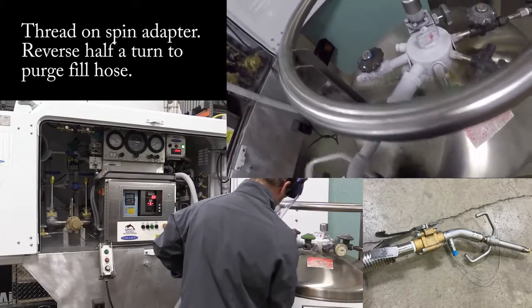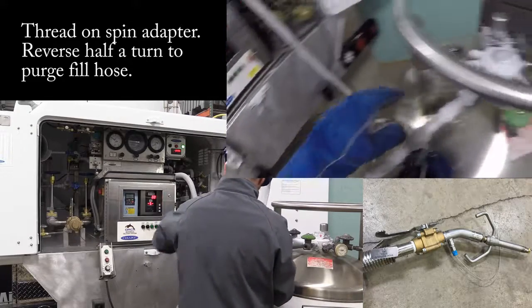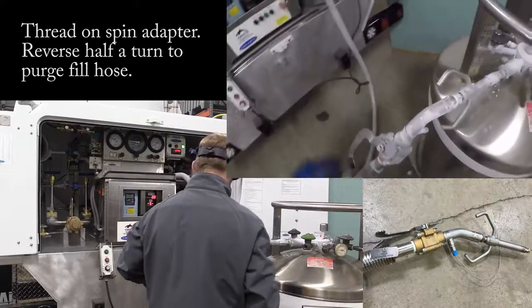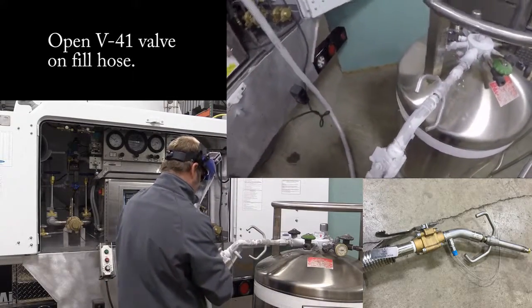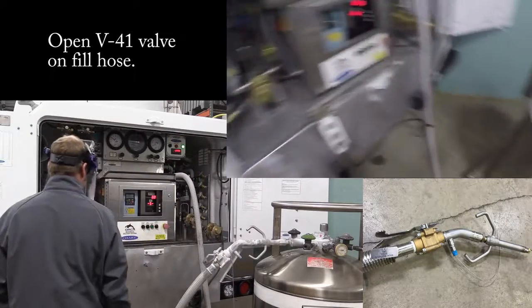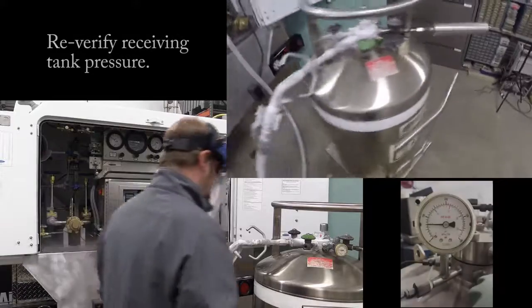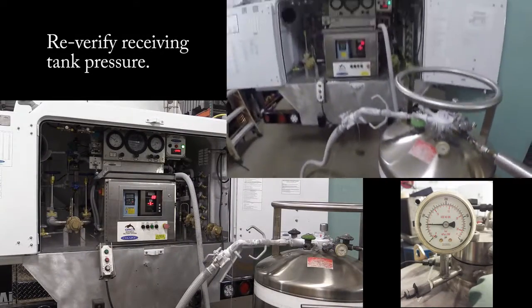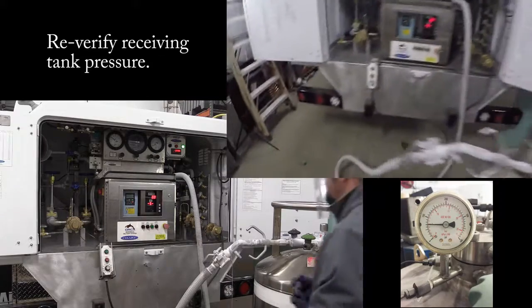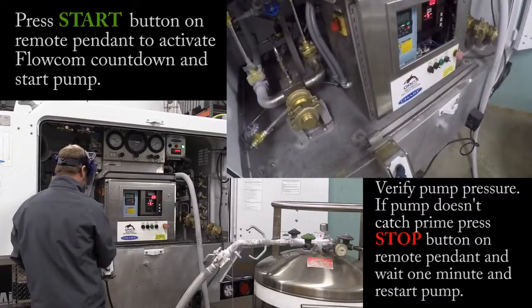You want to get it tight and then go back a turn. Open this valve. You can hear a little pressure — that's normal, there's about 5 PSI inside that hose. I check my pressure again; I'm just still under 100 PSI, so I'm going to feel comfortable at about 150, which is about in the middle of the pendant as well.